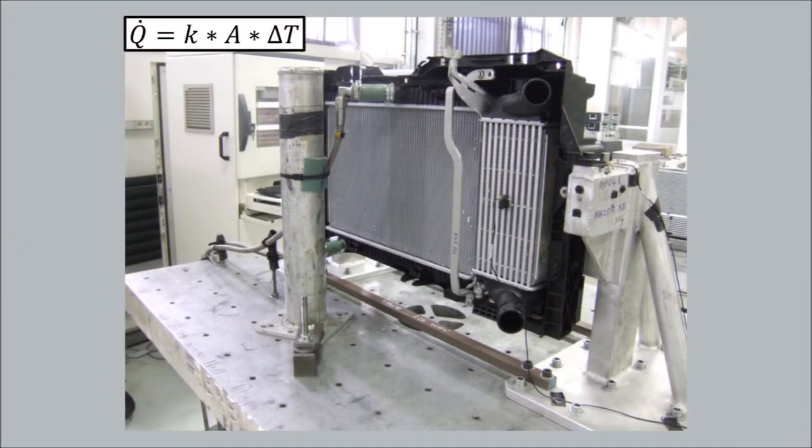If there is a new radiator, it will be tested on a test bench first. The area and temperature difference are known, and the heat flow can be measured. So the k factor can be worked out and then be used in simulations.